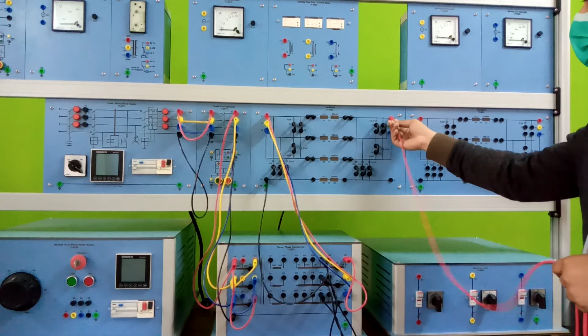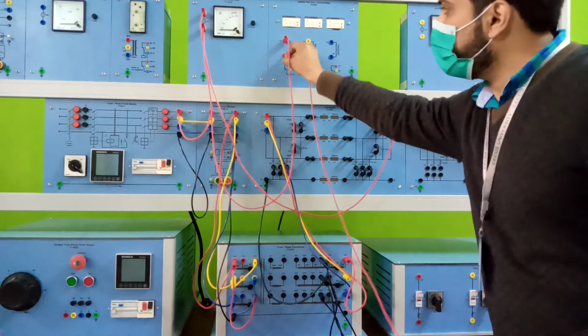First, for the red phase, it will go through the ammeter. My assistant will connect it to the ammeter, and the wire from the ammeter will be connected to the definite time over current relay. So from the load to the ammeter, from the transmission line to the ammeter, and from the ammeter to the relay. From the relay, this will be connected in series with your load.